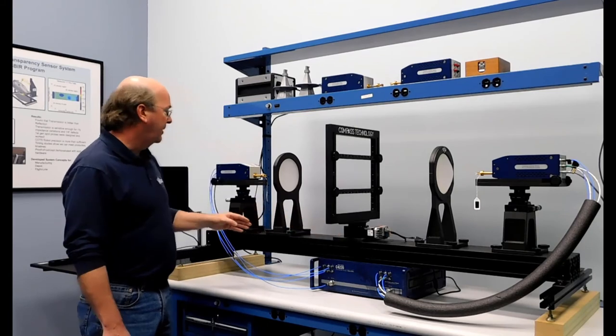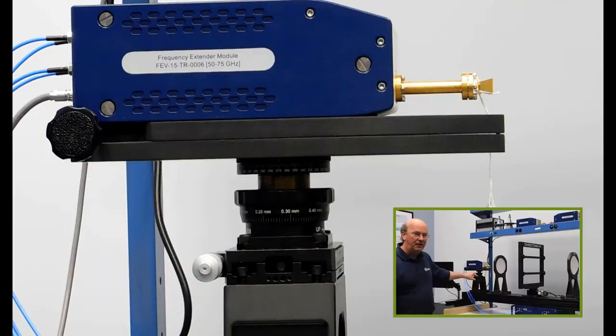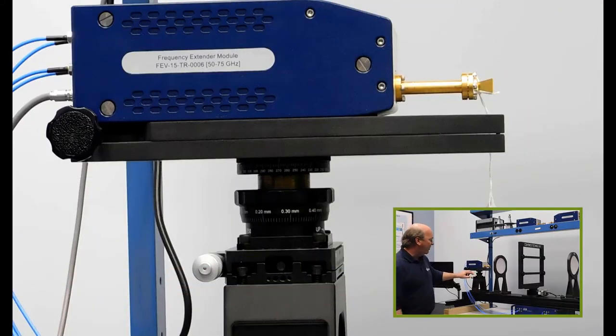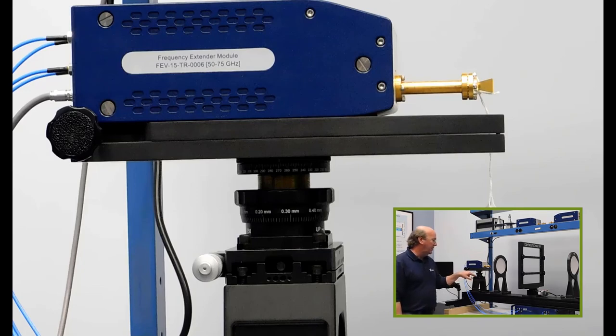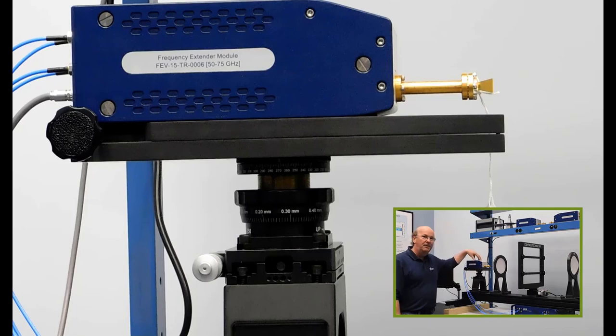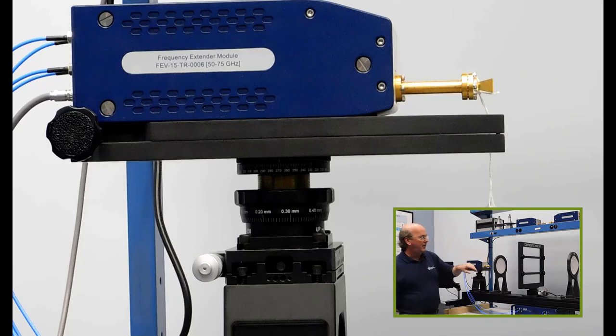As you can see this also has some additional features not on the other system. We have a micrometer stage here that allows us to do both fine rotation and linear translation of the horn. And the reason for that is because it's difficult to align at very high frequencies. And so with these different translation stages we can align these so they're in a nice straight line.